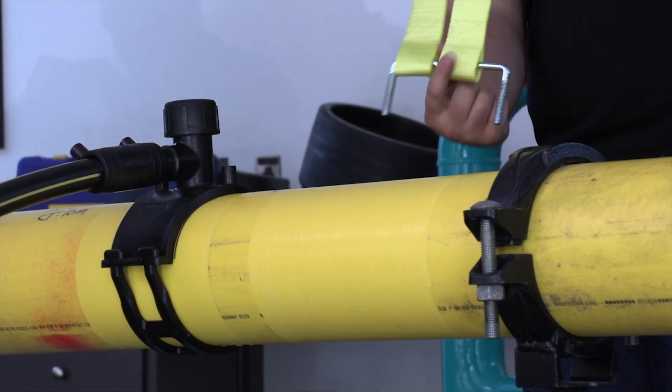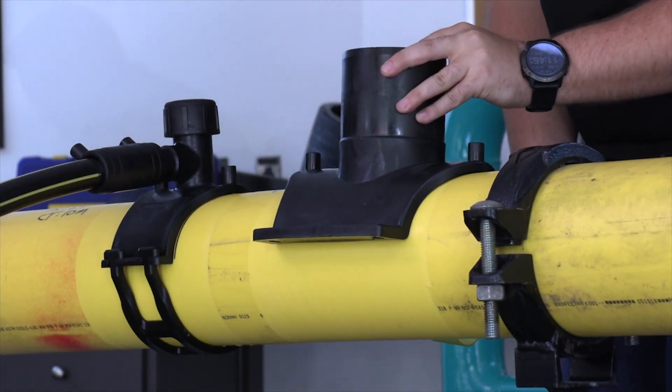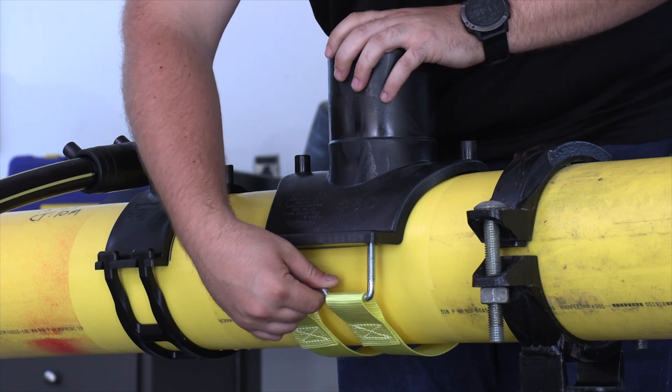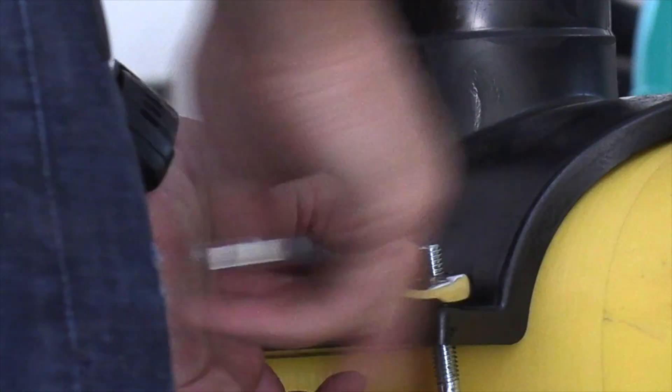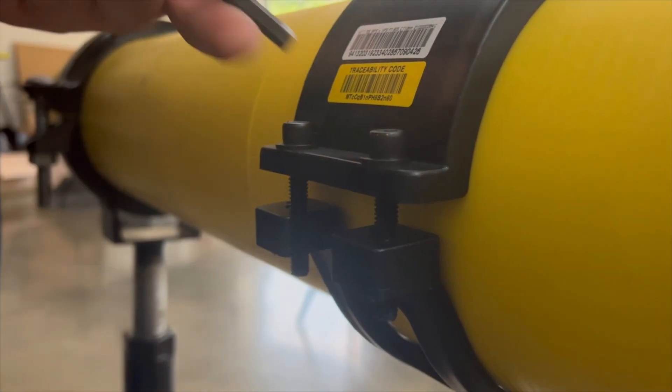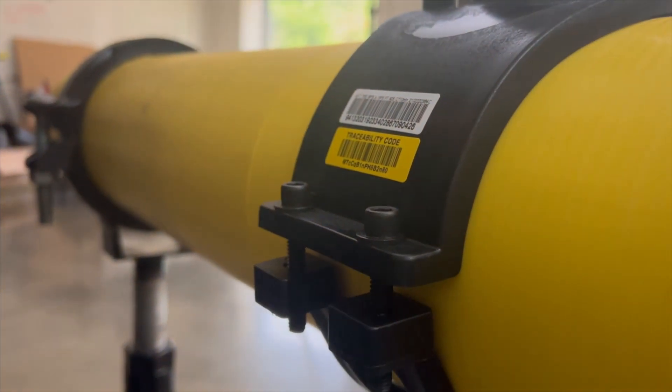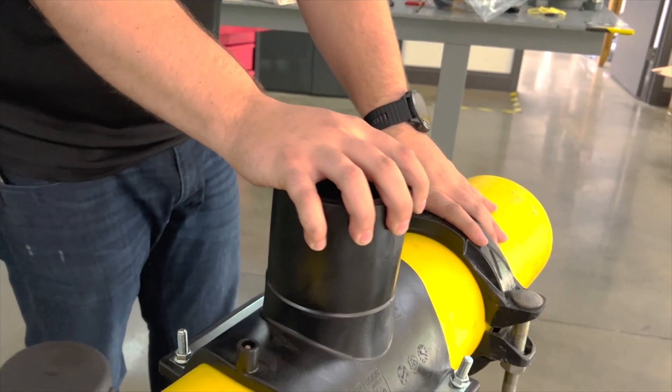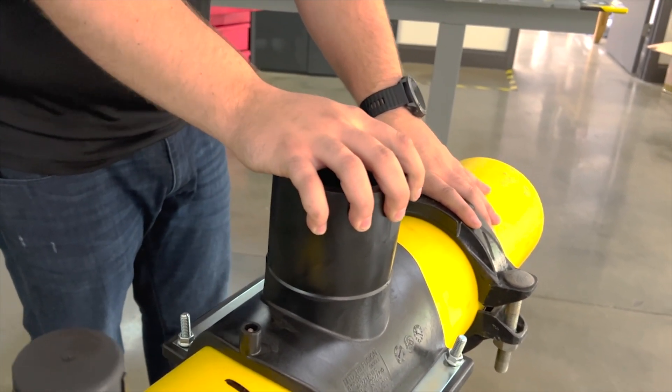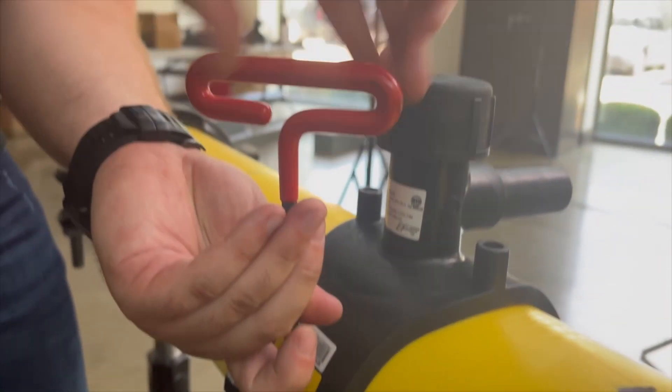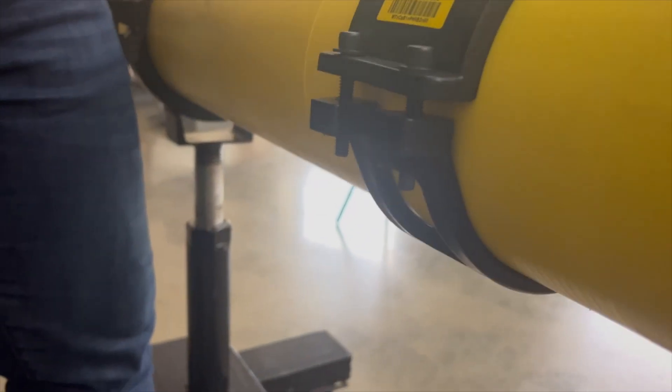For strap under clamps, remove the nuts from one side of the saddle, pass the U-bolt under the pipe and position the saddle as needed. Then reinstall the U-bolt in the fitting base and evenly tighten all four nuts to pull the saddle to the pipe. The tap tee is sufficiently tight when it doesn't move around the pipe when pushed with reasonable force. These screws are not designed to be bottomed out and if bottomed out they will likely be over tight, which may lead to fusion failure.